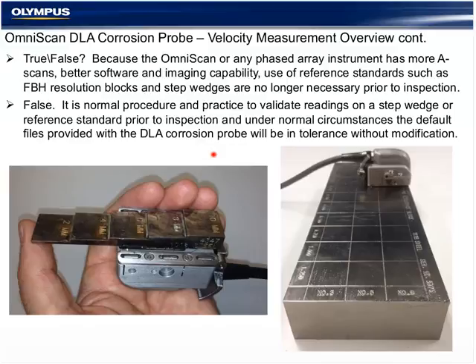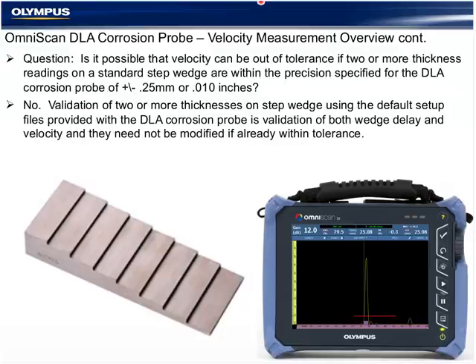To our knowledge, there are no codes or standards that actually make you adjust your setup from a wizard as opposed to validating the thickness readings, which is a validation of linearity and velocity and wedge delay. So is it possible that the velocity can be out of tolerance if 2 or more thickness readings on a standard step wedge are within the precision specified of 0.25 millimeters or 10 thousandths? The answer is no. If I were to check the step wedge here and here, and those readings are within tolerance, I can assume that the readings in between them are within tolerance, and that is not possible if the velocity were not close and the wedge delay was not accurately entered or predicted prior to setting it on the step wedge.